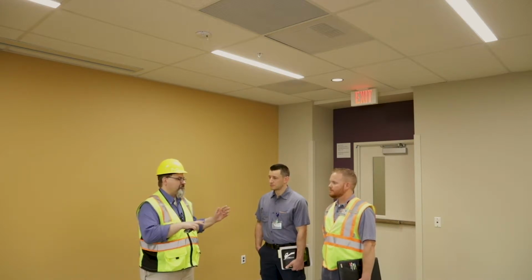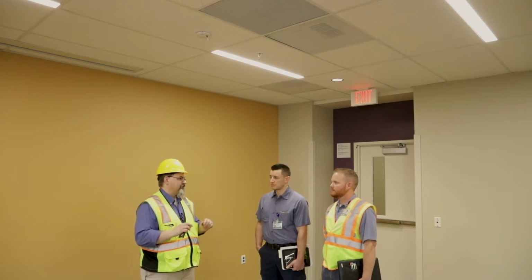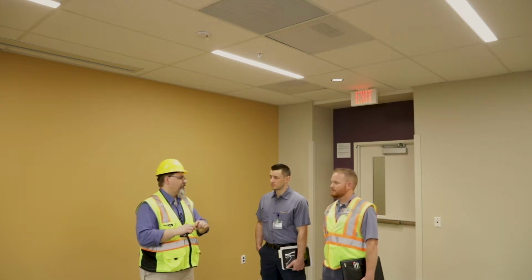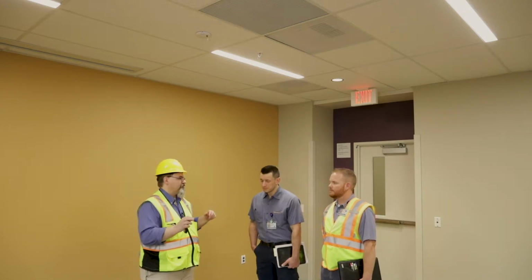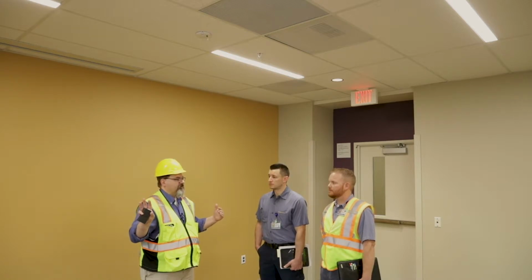A lot of times you'll see, hey, there's a daisy chain of devices, something's broke, the power's still on to all the devices, but one of them's got a mixed up Cat5 or something like this, or we've nicked a wire. You can just unplug things, and when things start making sense again, then you know that part of the network is good. You see what I'm saying?